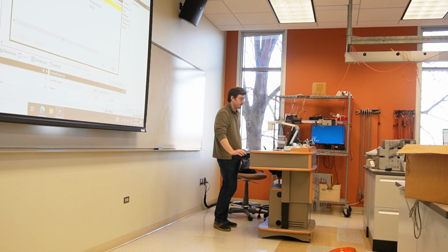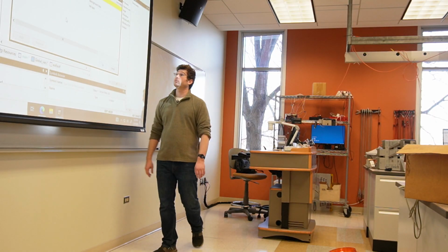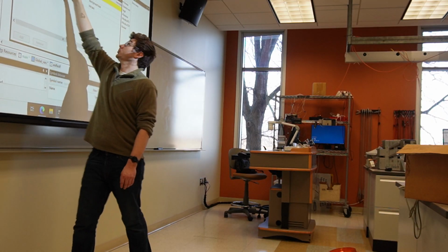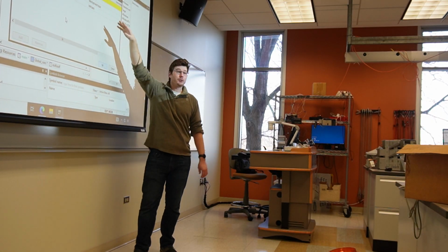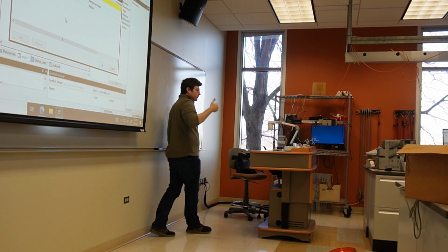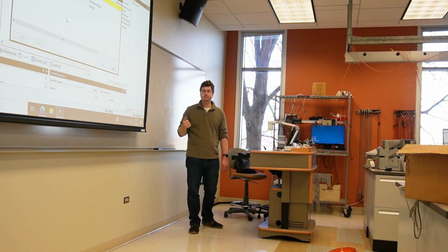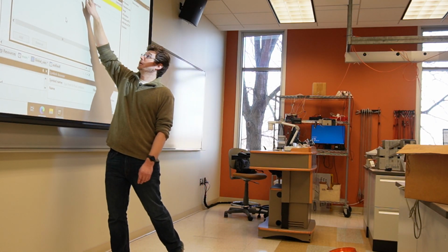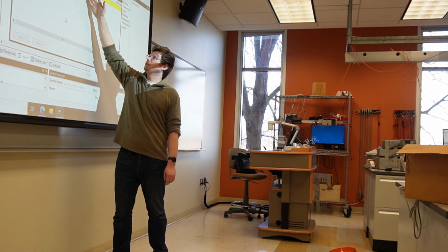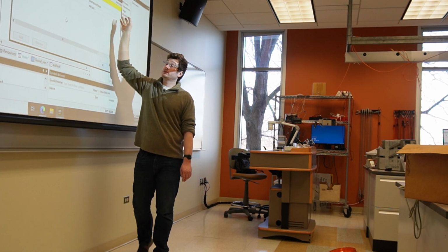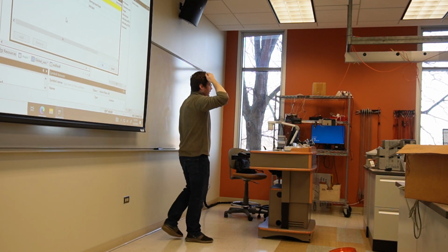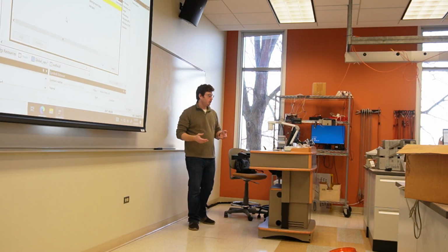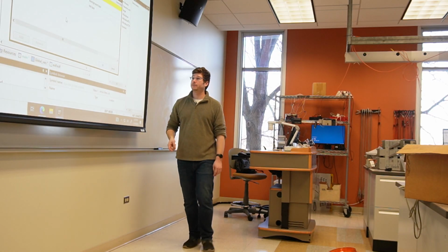So as we see here, main is in the fast task group. And we can see here, the period for each of these groups is set differently. So when a program is in the fast task group, every 10 milliseconds, it'll run that program. So count, every 10 milliseconds is increasing by 1, that variable. So 1,000 times a second, right? Or 100 times a second. If we put something in a slow task, that'll run 10 times a second. If we put something in the background task, it'll run once every 5 seconds. That might be like checking in on something that doesn't change very often, running a calculation that doesn't have to be run that often, something that doesn't change at the blink of an eye, right?